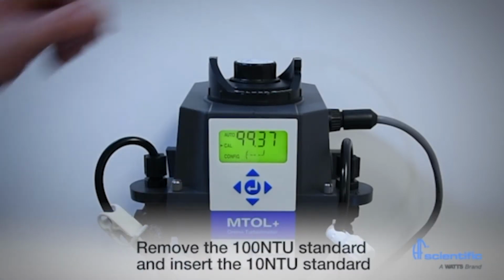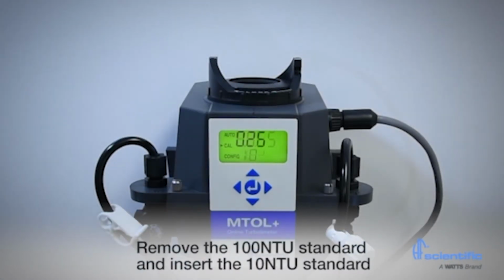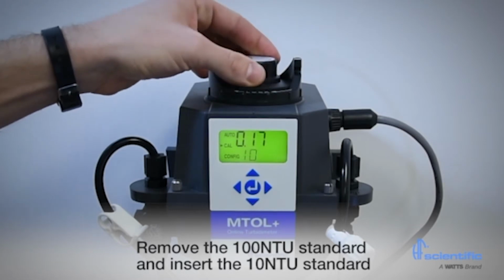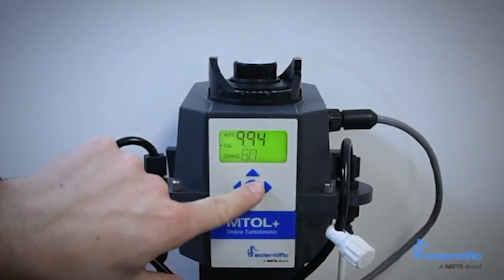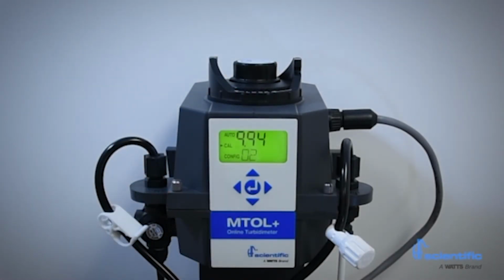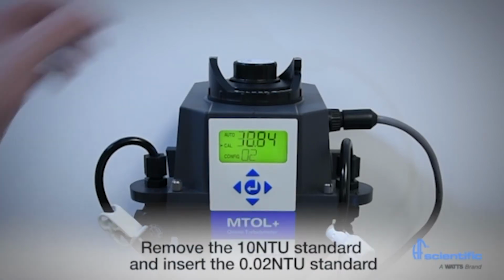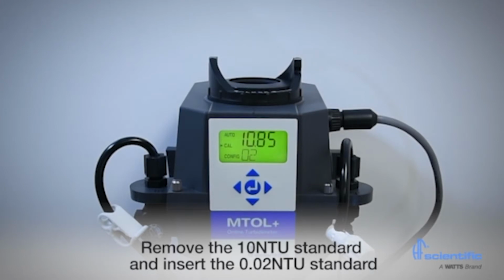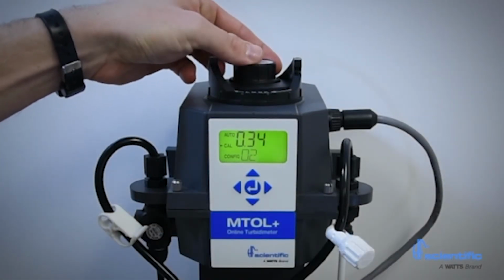Next, remove the 100 NTU standard and insert the 10 NTU standard. Press the center button. The display will count down 60 seconds and then display 10. Remove the 10 NTU standard and insert the 0.02 NTU standard. The display will count down 30 seconds.